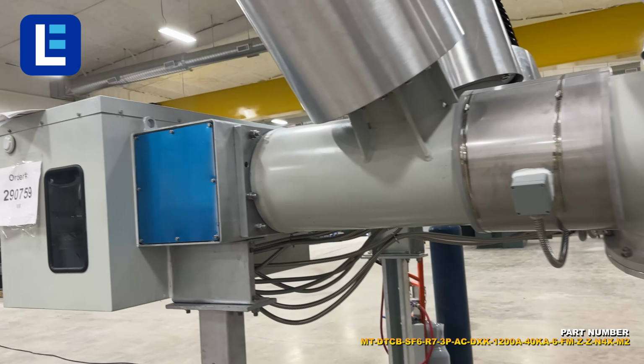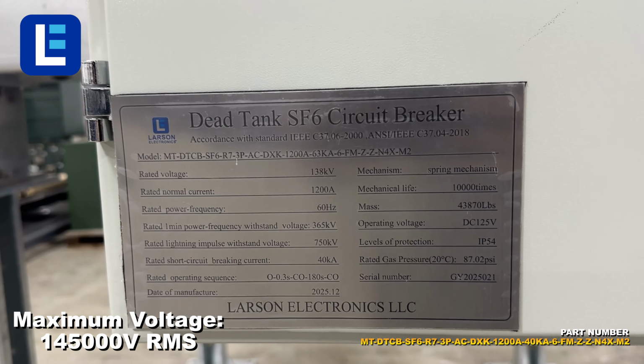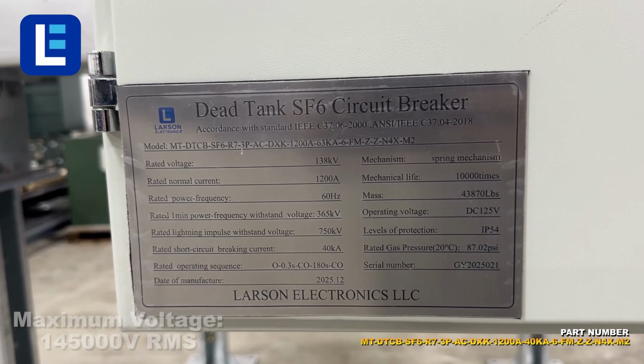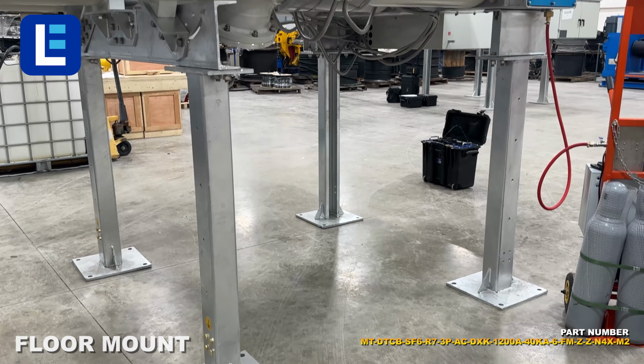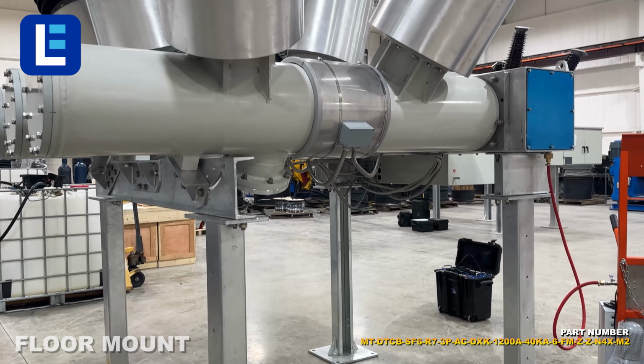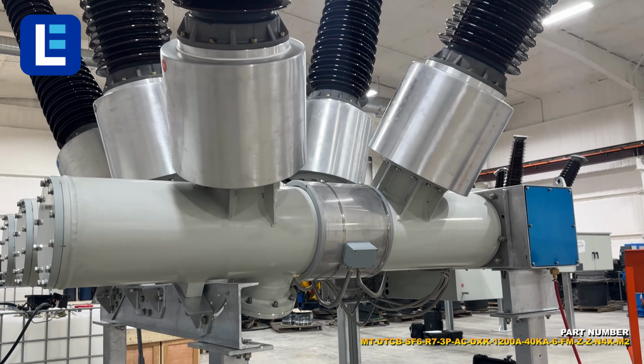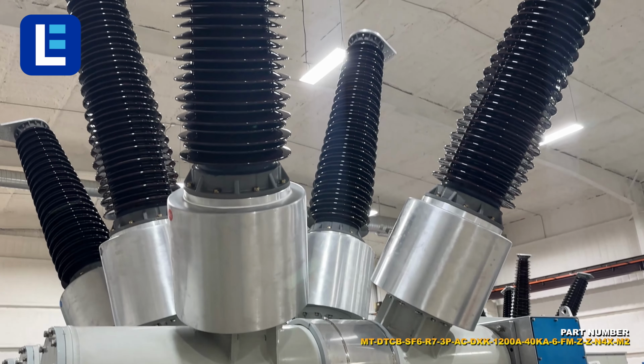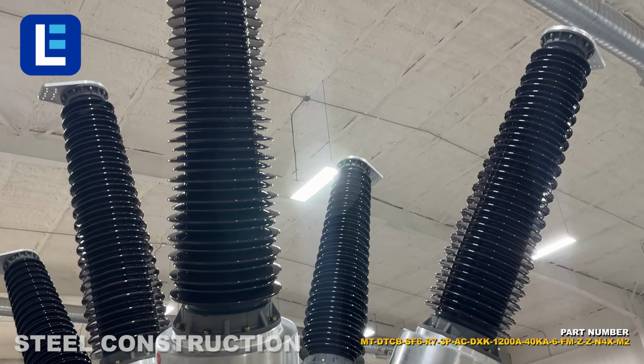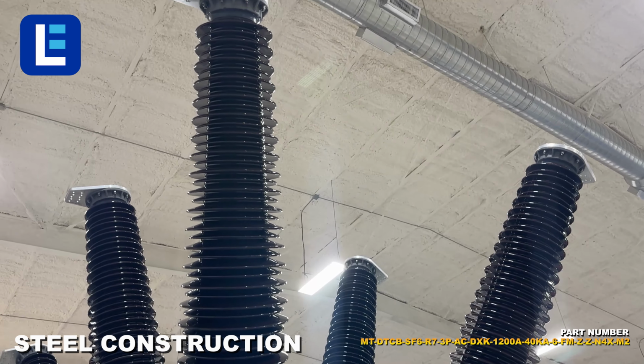The nameplate located on the front panel enables all circuit breaker characteristics to be identified. Compatible with 3-phase 145,000 volt AC, this 3-pole circuit breaker carries a 1200 amp rating at 138,000 volts AC.